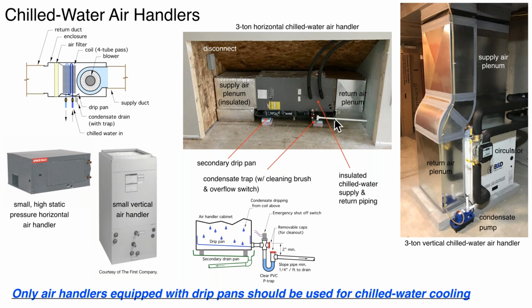And then once a year, when you take a look at this unit, make sure that you run the brush through that condensate trap. It's going to get some algae, and again, I'm not a biologist, so I'm not sure if algae is the correct term, but you're going to get some slime that just builds up in that trap. Most of these traps are supplied with a small brush, and you just pop the cap off and run the brush through there a few times and clean it out.